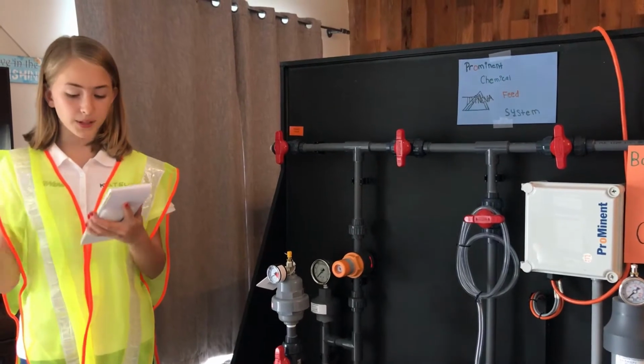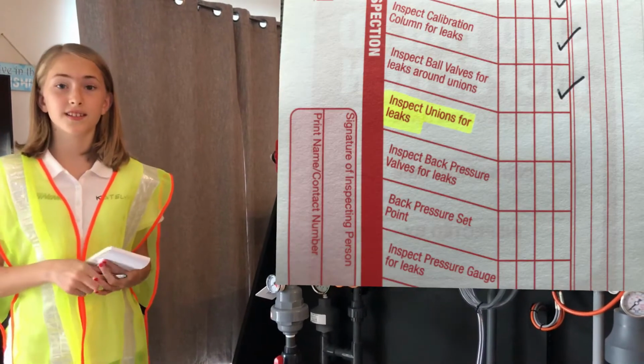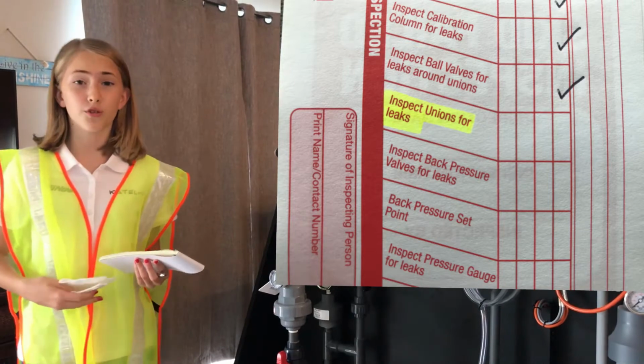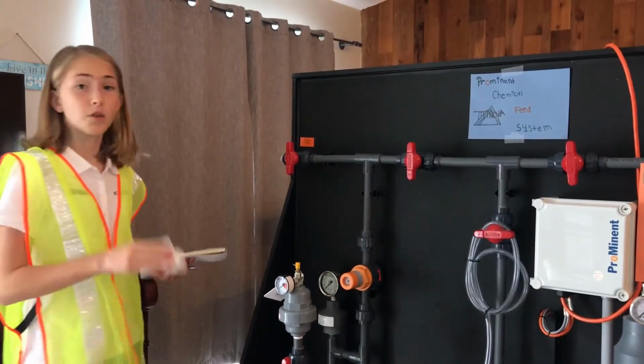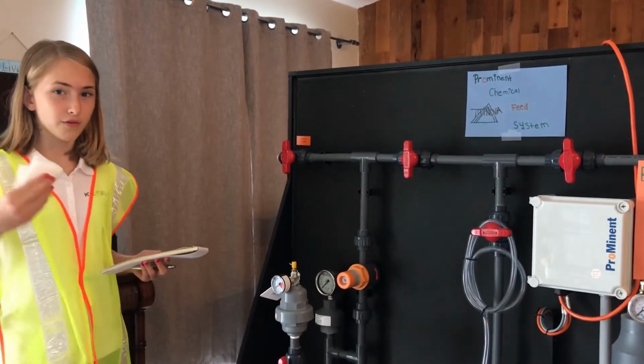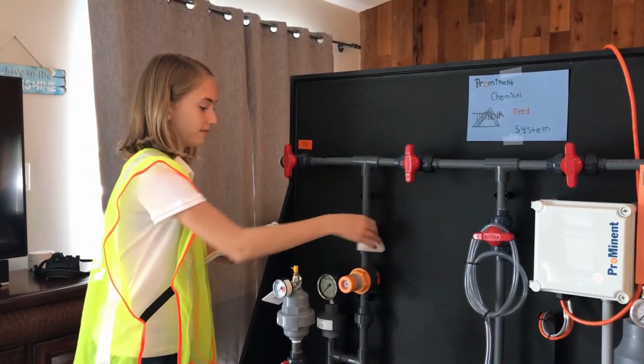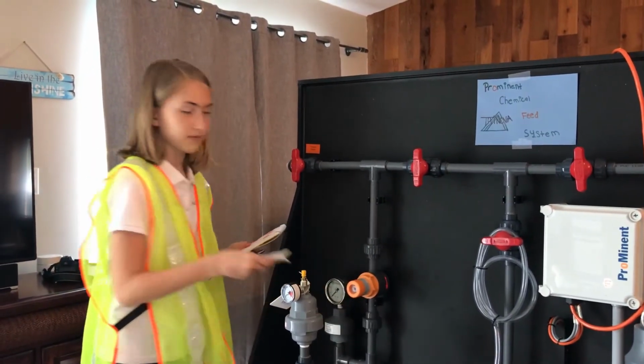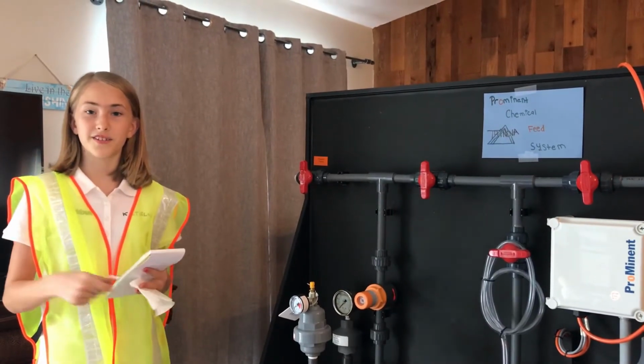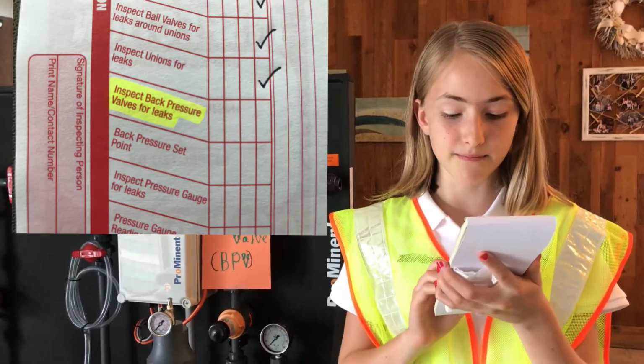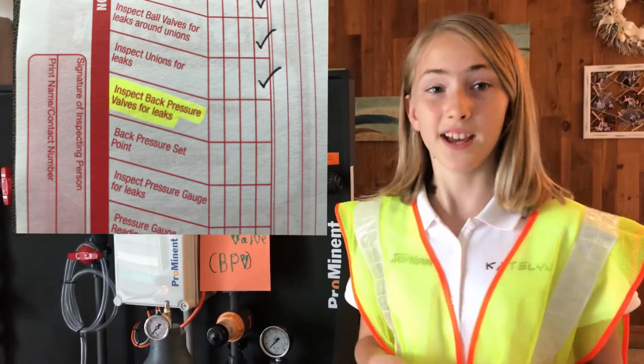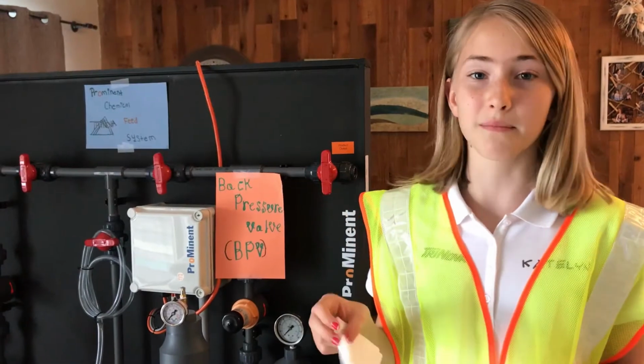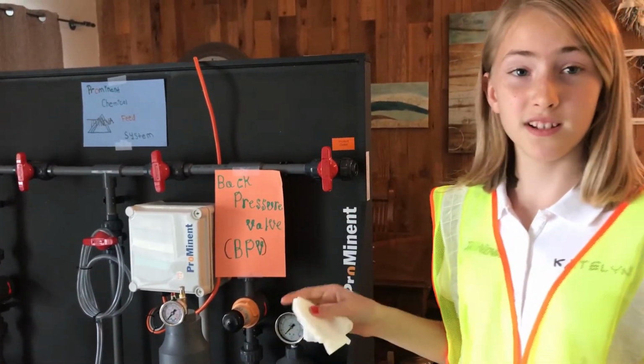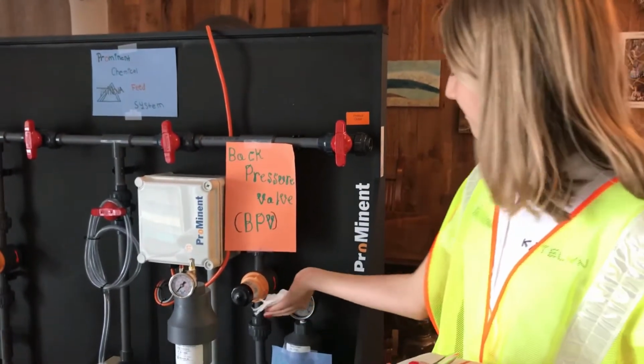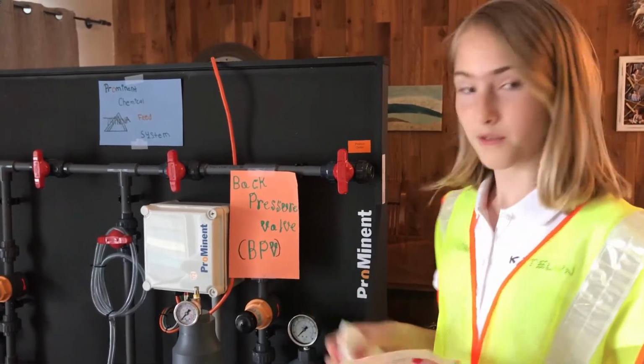Step 11 on your booklet is to inspect unions for leaks. That includes crystallization, moisture, water, or dampness. There will be multiple unions, so make sure you check all of them. And as you can see, we're good, so there's another check mark. Step 12 on your booklet is inspect back pressure valves for leaks. Again, any crystallization, moisture, water, or dampness. We're going to inspect the 2 pieces and the ends. And we are good.